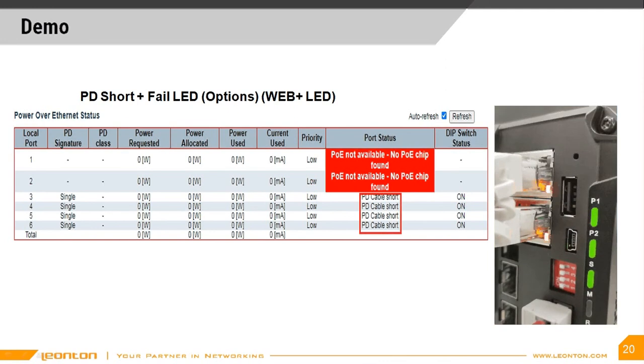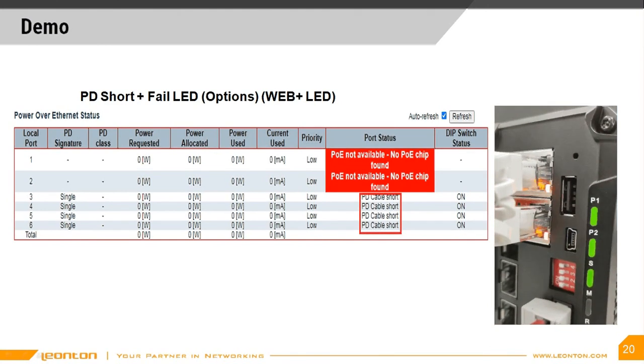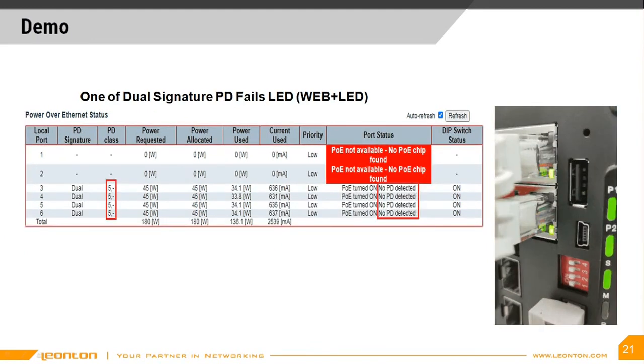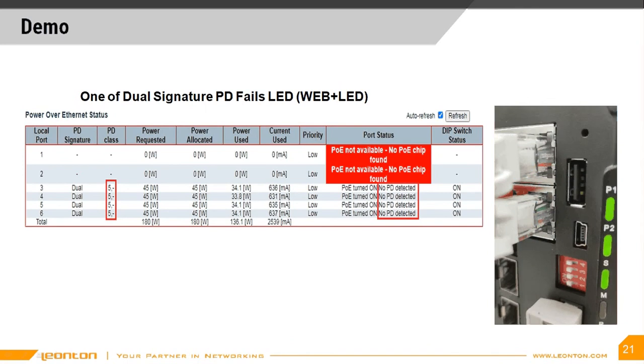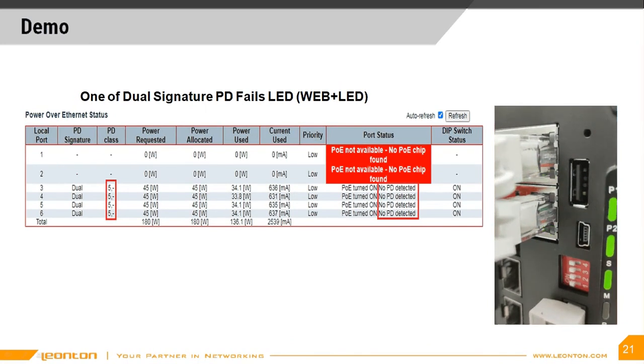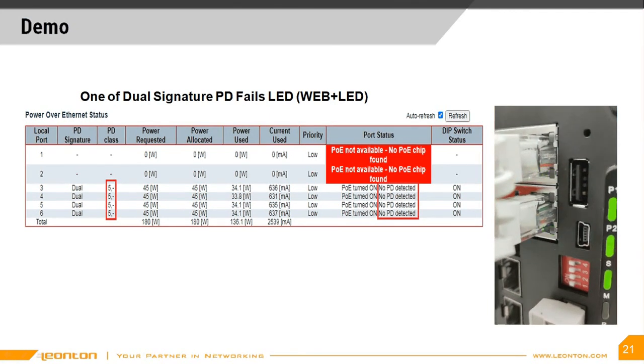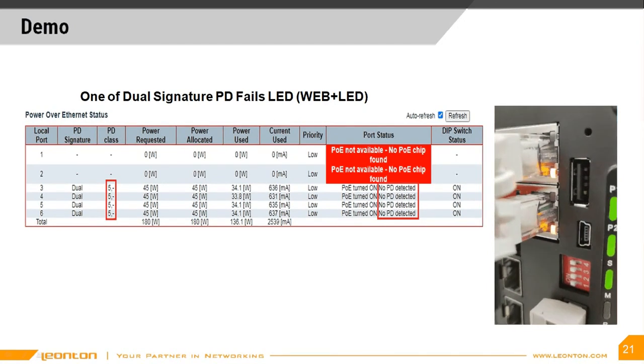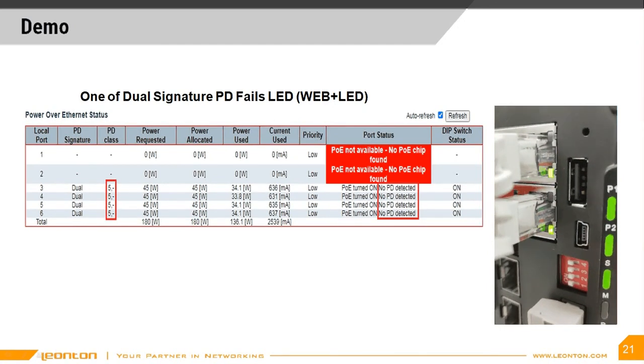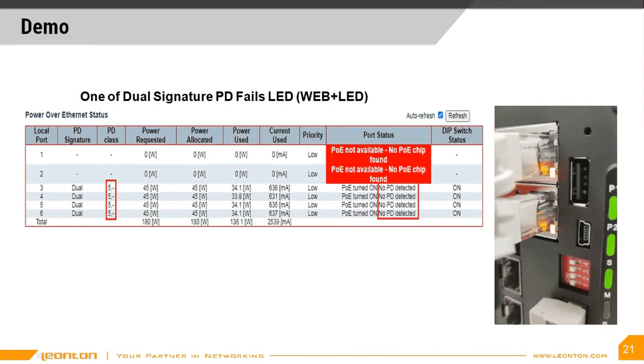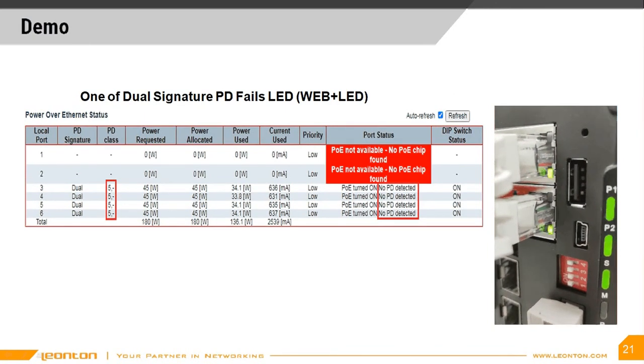Here's a scenario where we have short circuits in all Ethernet cables. Therefore, all port LEDs are flashing orange, green, orange in sequence, with a one-second delay without flashing between each sequence. In this scenario, the emulation is based on only one of the dual signature PDs working correctly in each power device. The other signature PD in each power device is either malfunctioning or invalid — where invalid represents a situation where the power classification of a signature PD cannot be identified. Therefore, all port LEDs are flashing green, orange, green in sequence, with a one-second delay without flashing between each sequence.